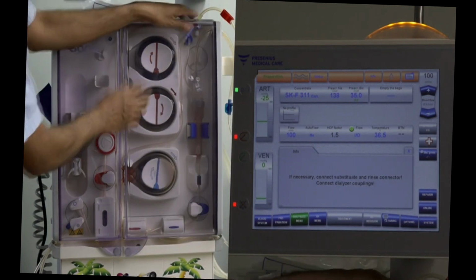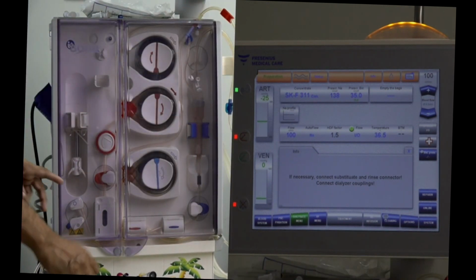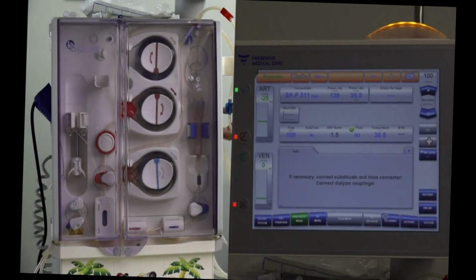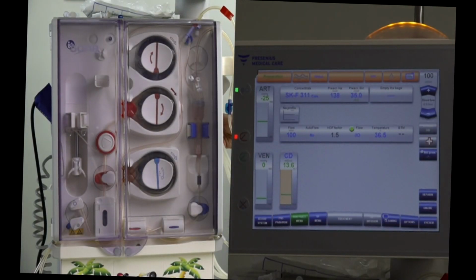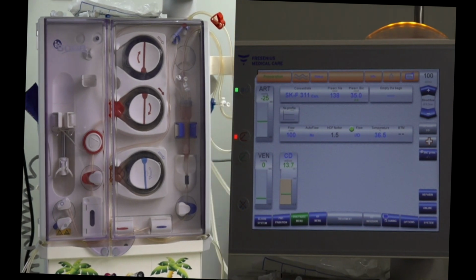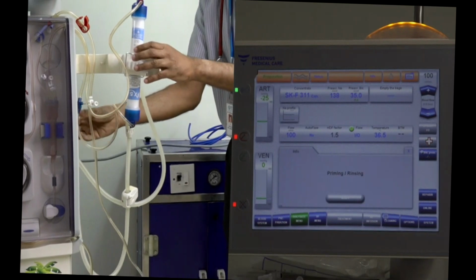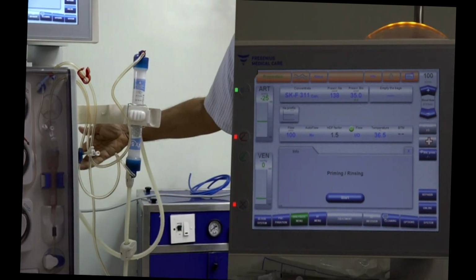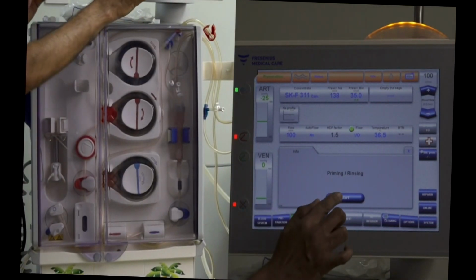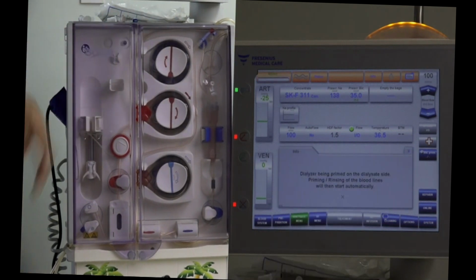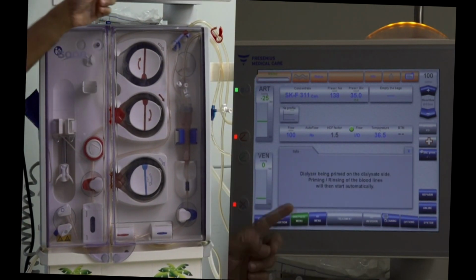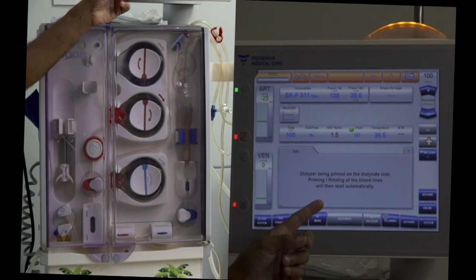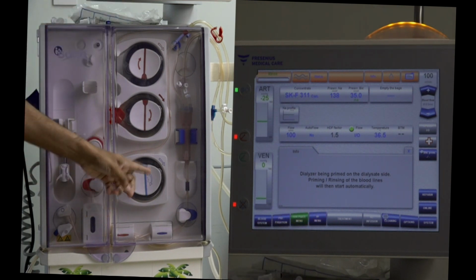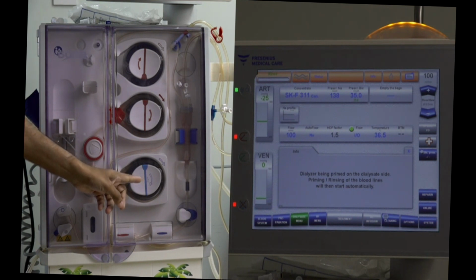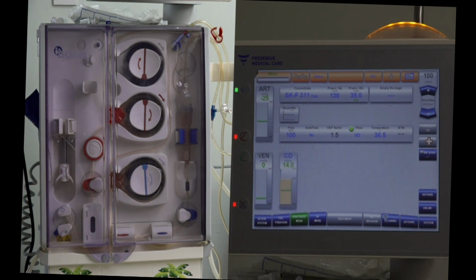and there's one more message that the machine is giving, and that is to connect the dialyzer couplings. So this is Fresenius, red to blue and blue to red, like with any other conventional dialysis. We close the flap, machine says start priming or rinsing. So I'm going to start. So now the machine says it is priming the dialyzer on the dialysate side, after which it is going to automatically start the substitution pump and prime the blood side.